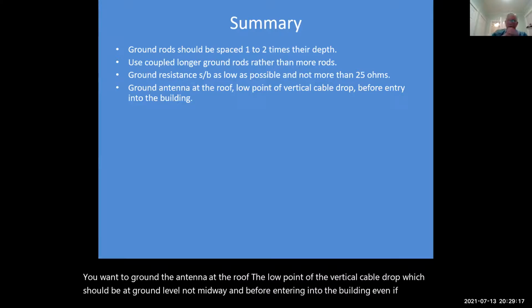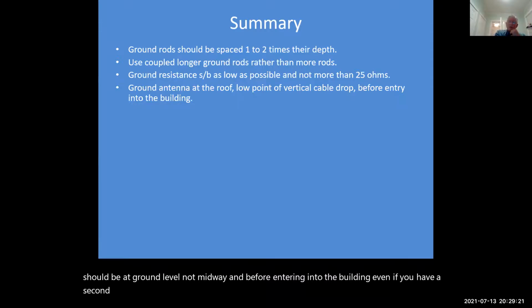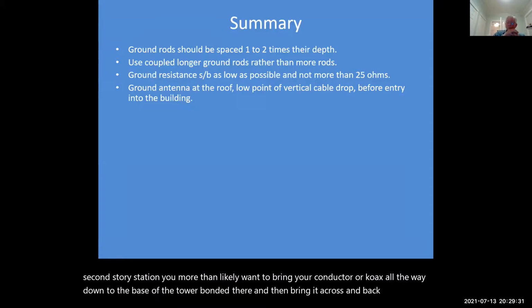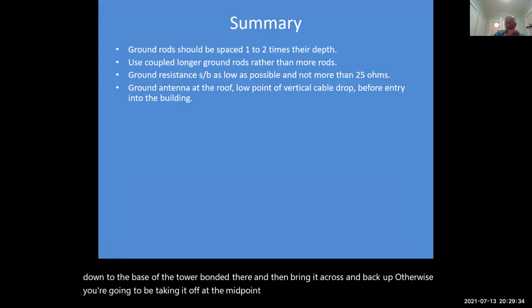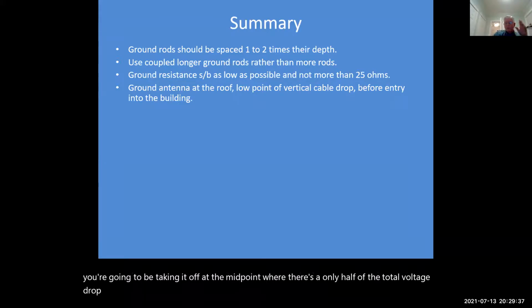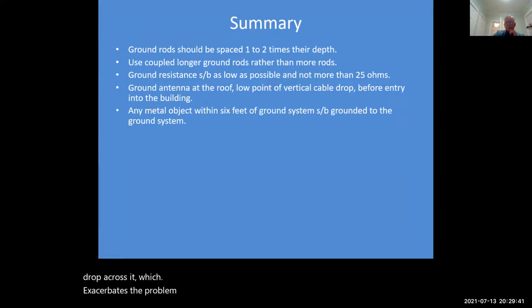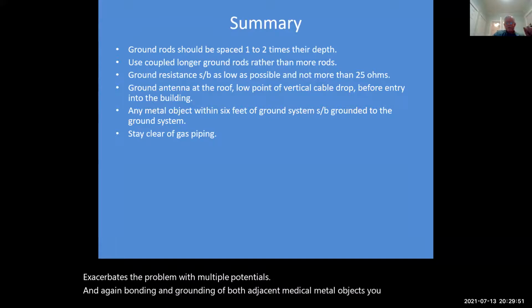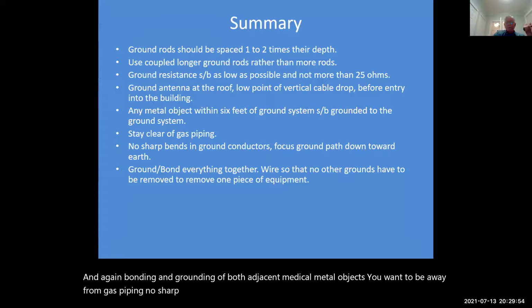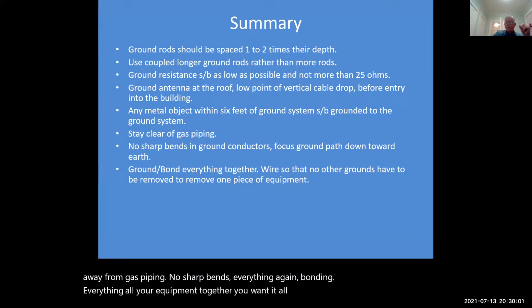Even if you have a second story station, you more than likely want to bring your conductor, your coax, all the way down to the base of the tower, bond it there, and then bring it across and back up. Otherwise, you're going to be taking it off at the midpoint where there's only half of the total voltage drop across it, which exacerbates the problem with multiple potentials. And again, bonding and grounding of adjacent metal objects. You want to be away from gas piping, no sharp bends, everything. Again, bonding everything, all your equipment together, so that there's equal potential between them.